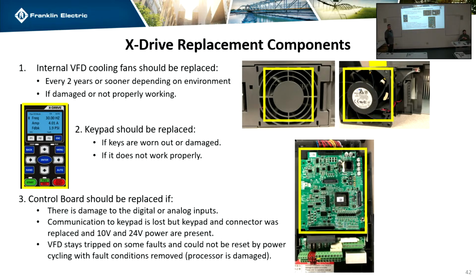What we run into, guys, is that you can't pull the drive off the wall and just say it's bad. We need a case number, and we need the guys at tech support to say it's bad. Get the case number, then you bring the drive back, and then we can get you a new drive. The tech support team can usually solve things in the field. A lot of times it's programming, a parameter set wrong, or something silly like that. It can be easily solved, so that's the whole point of having people call. We want at least an attempt at troubleshooting before we start bringing stuff back to warranty evaluate it.